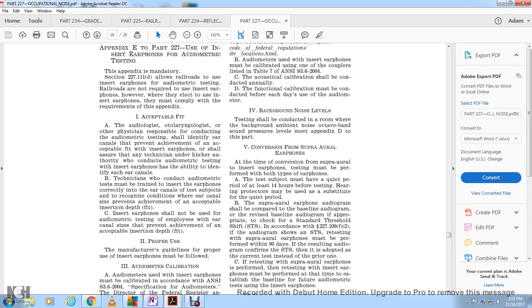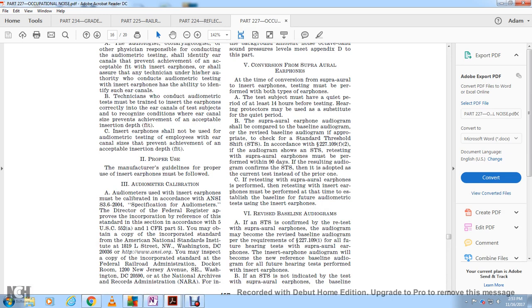If the audiogram shows an STS, retesting with supra-aural earphones must be performed within 90 days. If the resulting audiogram confirms the standard threshold shift, the current test is adopted instead of the prior one. When retesting with supra-aural earphones is performed, retesting with insert earphones performed at the same time establishes the baseline for future audiometric testing using insert earphones.